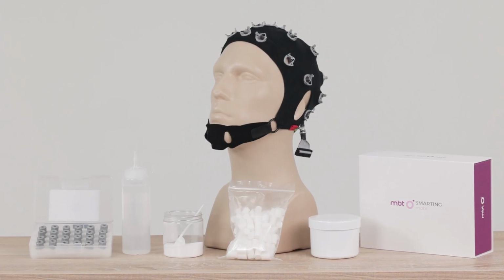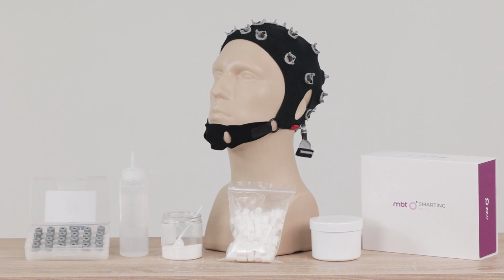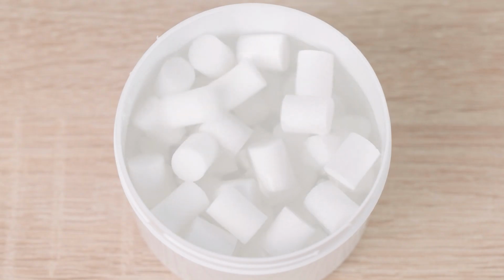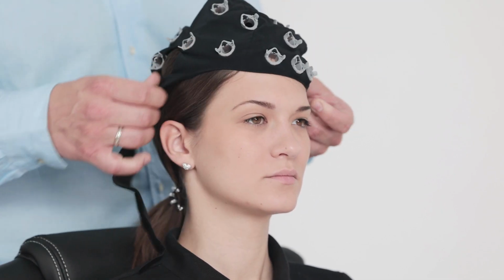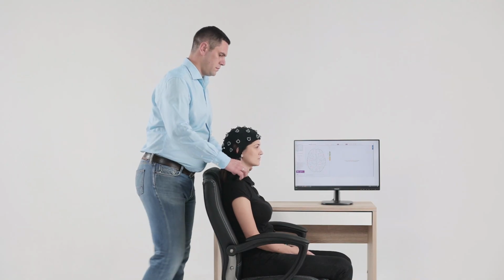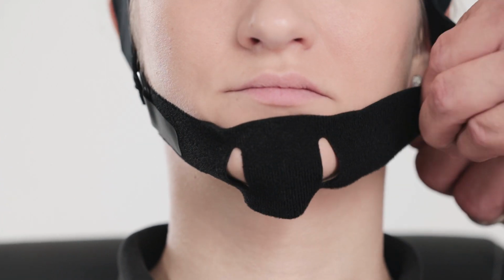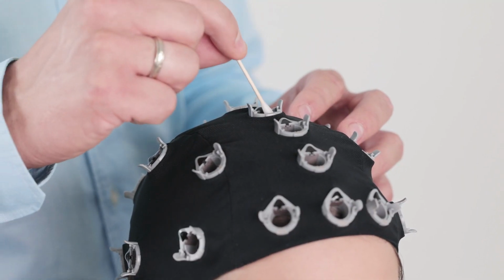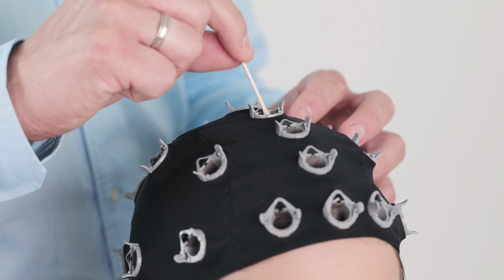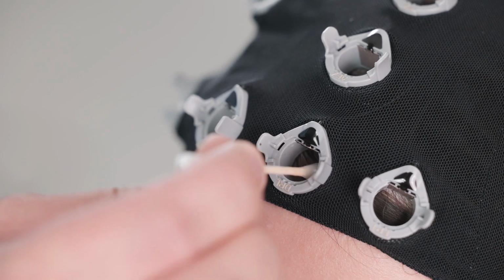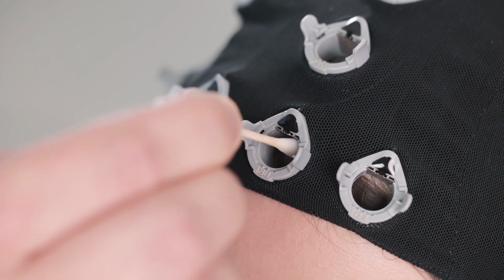In this approach, the empty cap is first placed on the subject's head and then the sponges are mounted. First, mount the electrode cap on the subject's head and gently tighten the strap around the chin. Immerse a cotton swab in the saline solution. Split the hair on the electrode location sites and wet the scalp.